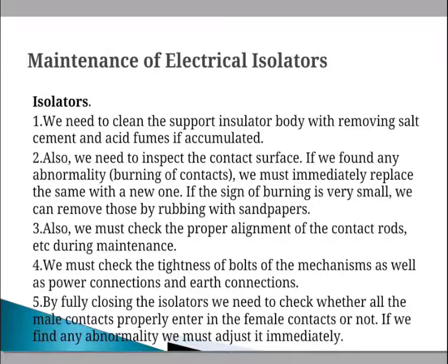For maintenance of the electrical isolator, clean the support insulator body by removing salt, cement, and acid fume deposits if accumulated. Inspect the contact surface — if any abnormalities are found, immediately replace with a new one or repair it. If signs of burning are minor, remove them by rubbing with sandpaper.